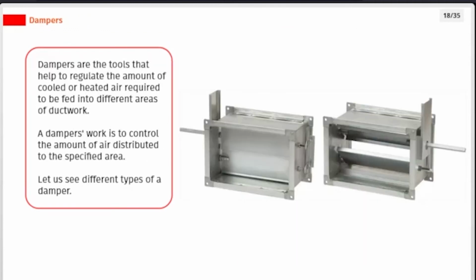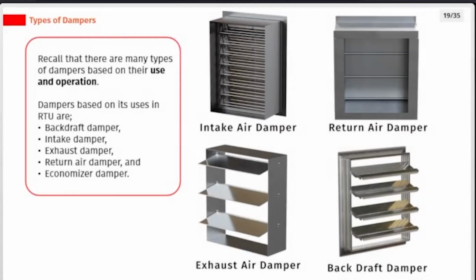Dampers are the tools that help to regulate the amount of cooled or heated air required to be fed into different areas of the ductwork. A damper's work is to control the amount of air distributed to the specified area. Let us see different types of dampers. Recall that there are many types of dampers based on their use and operation. Dampers based on their uses in RTU are backdraft damper, intake damper, exhaust damper, return air damper, and economizer damper.